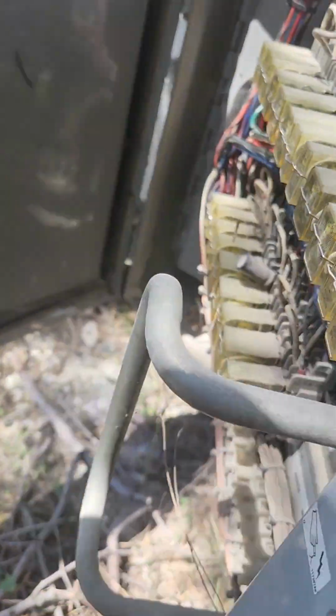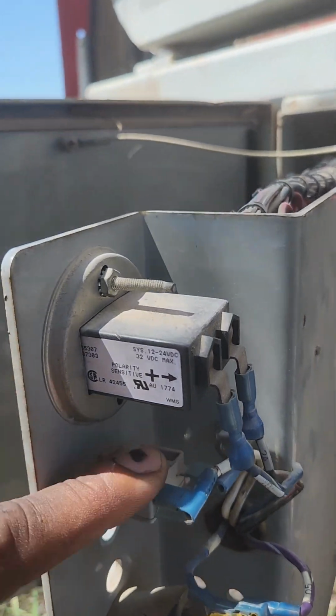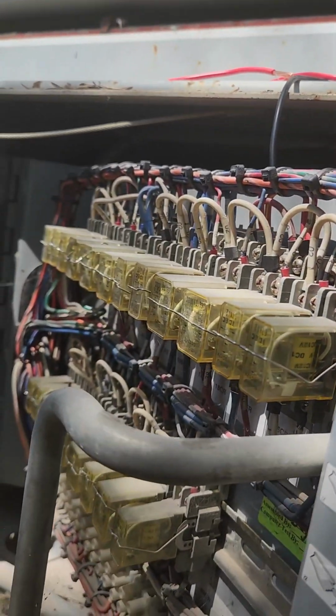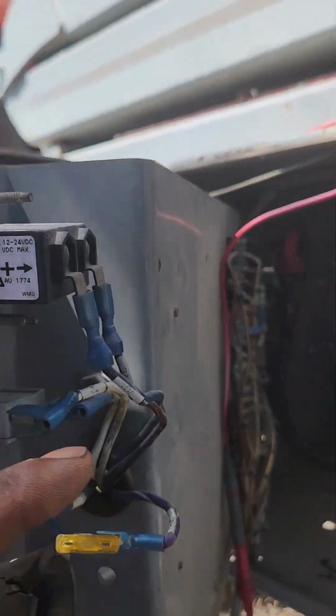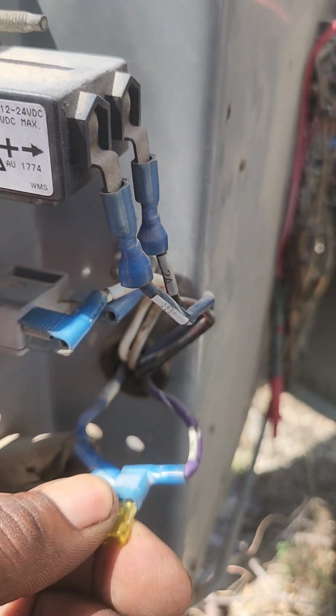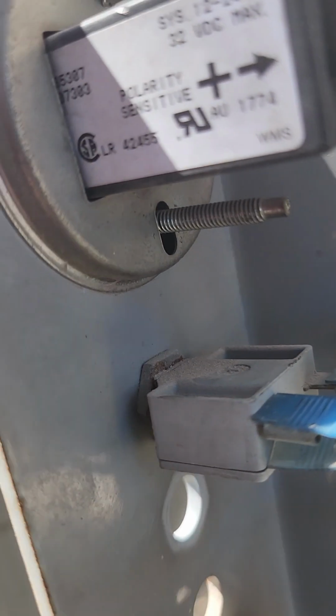We checked all the relays. The relays are good. We found it's got a circuit breaker here, and here it's missing one circuit breaker, but there's a fuse in its place and the fuse is blown. So to test it, we're going to pull the fuse out and put in a wire there temporarily.